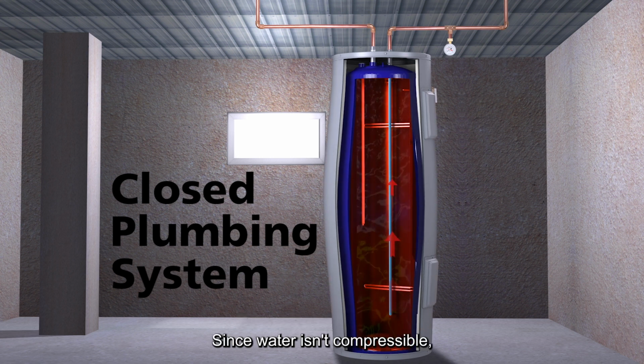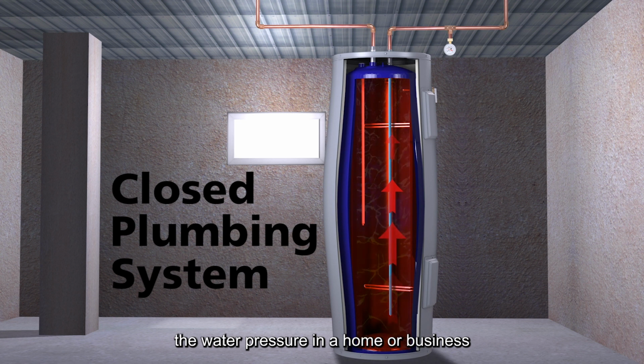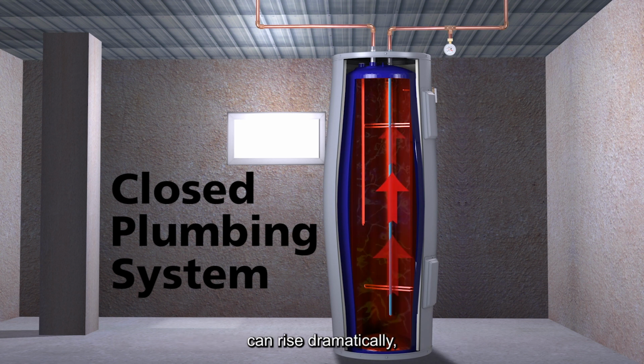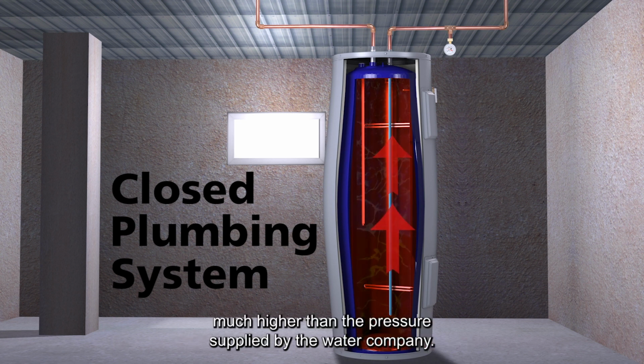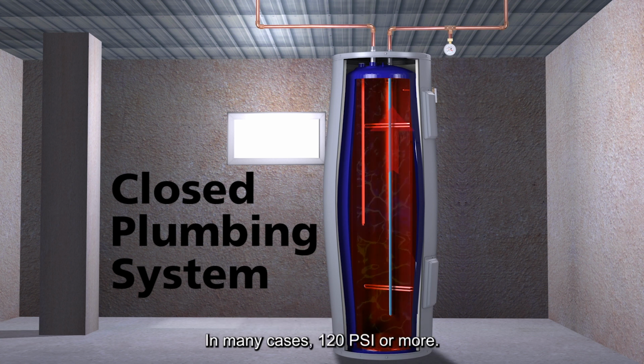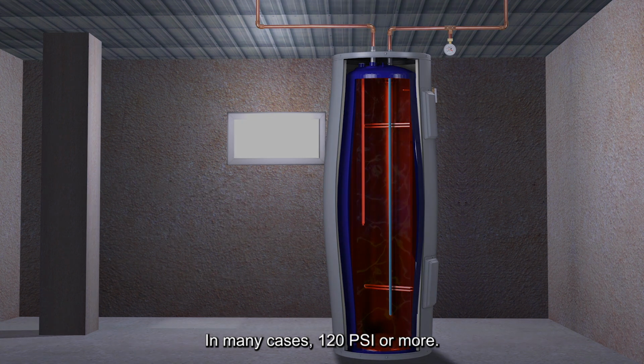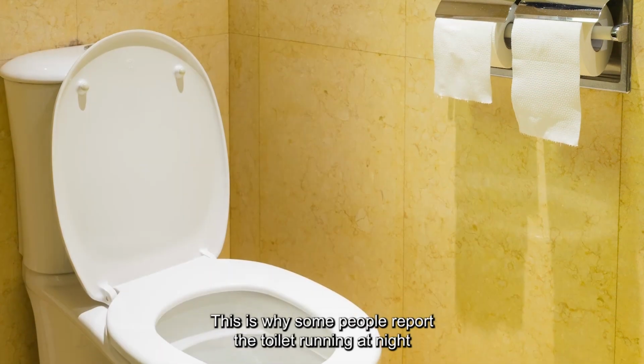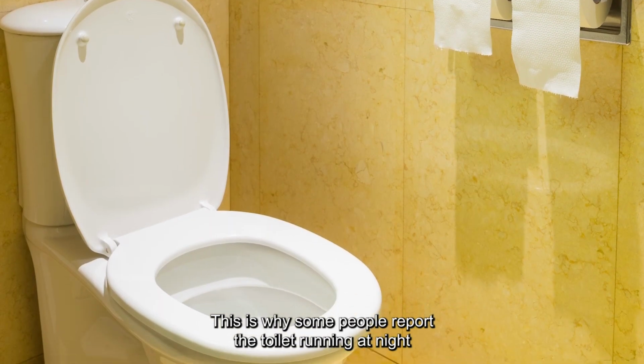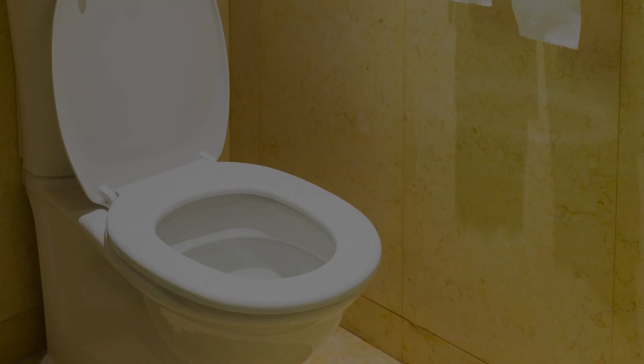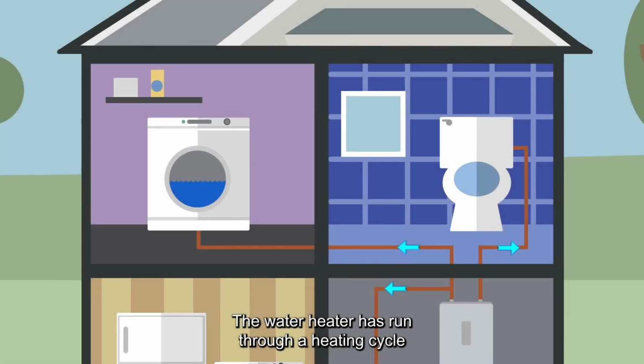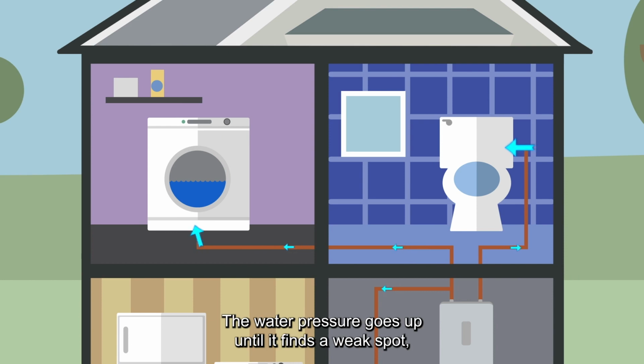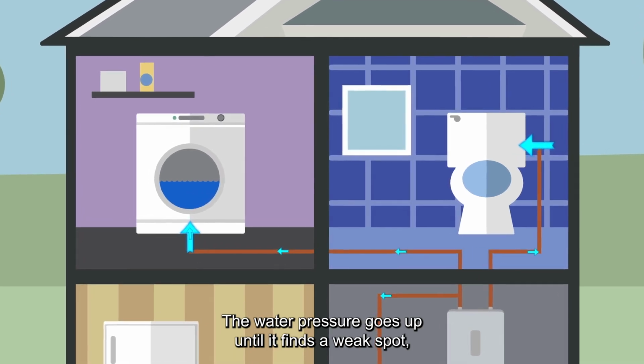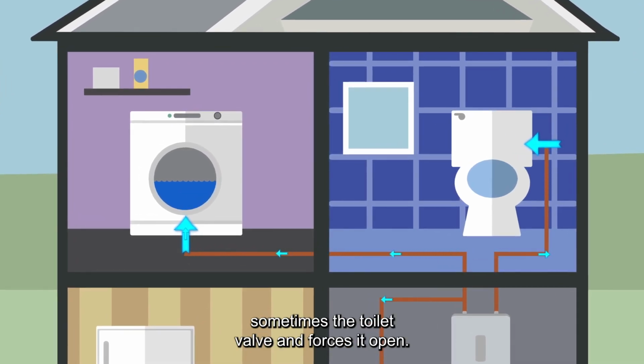Since water isn't compressible, the water pressure in a home or business can rise dramatically, much higher than the pressure supplied by the water company, in many cases 120 psi or more. This is why some people report the toilet running at night when no one has used it. The water heater has run through a heating cycle, and the expanded water can't escape the house. The water pressure goes up until it finds a weak spot, sometimes a toilet valve, and forces it open.